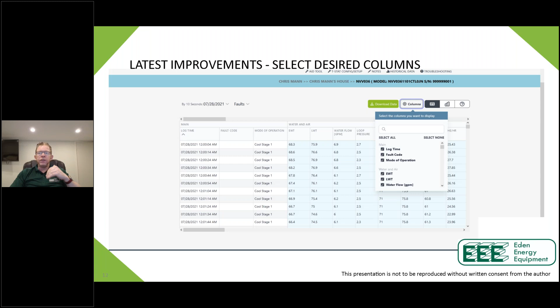I don't care whether I had a Y1, Y2, or O call, and I'm not sure I care about the outputs to the unit, since you can see a Y1 call and a compressor output call. Maybe we turn those off. We only care about seeing water temperatures and refrigerant data to figure out what caused this freeze protection lockout. So the addition of filtering by columns is a fantastic improvement that makes it a lot easier.